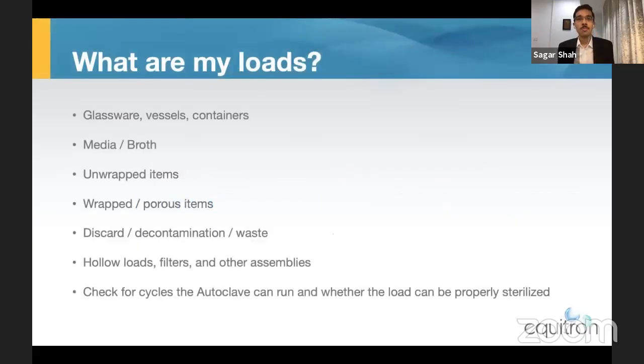So first up, what are the types of loads that you would be sterilizing? The autoclave you purchase should possess the cycles which are capable of sterilizing your specific loads. So it could be glassware, media, discard, wrap loads, hollow loads, filters, and various other assemblies. Now, autoclaves can primarily be divided into two broad categories: vacuum autoclaves as well as gravity, also called non-vacuum, autoclaves. Non-vacuum autoclaves are suited for sterilization of non-porous goods and liquids, whereas vacuum autoclaves are ideal for wrapped, porous, and hollow loads. Vacuum autoclaves will efficiently remove air from the chamber and the load, thus allowing complete penetration of steam to your critical loads.